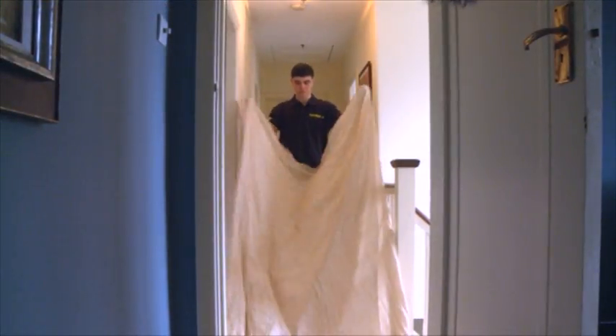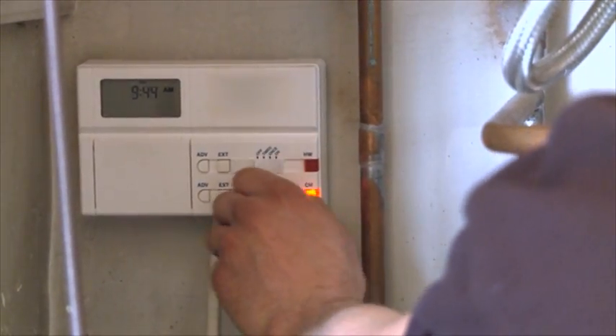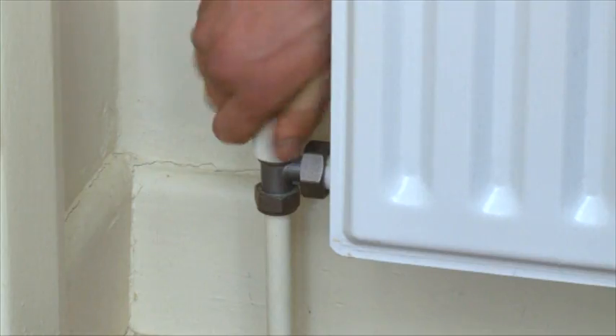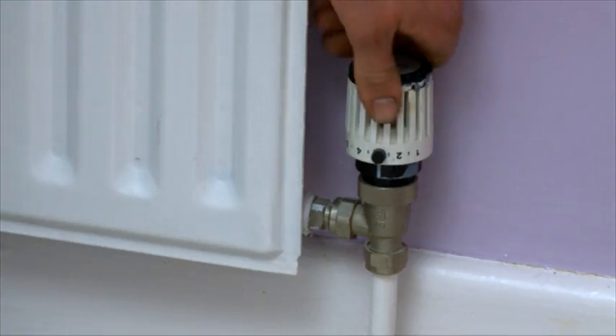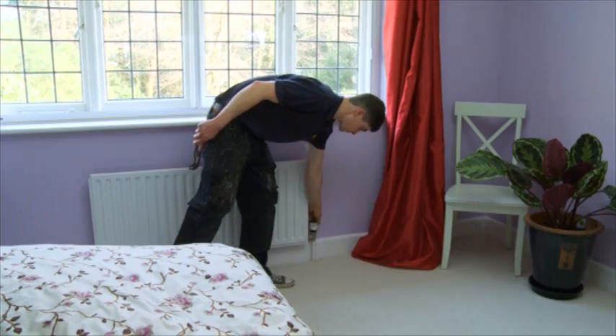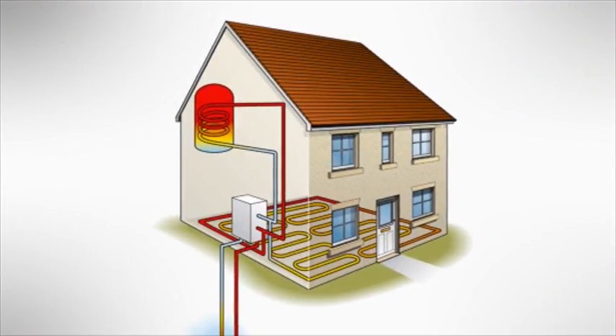Regarding the actual flushing process, firstly ensure that the system is correctly set up to use the power flush unit. Turn off all electrical controls and electrically isolate the system. Ensure that all radiator wheel head and lock shield valves are fully open, and remember to make a note of their position. Check that all thermostatic radiator valves or TRV heads are either set to maximum or removed, and that all zone valves and three port valves are locked open. Any anti-gravity valves should be bridged, bypassed or temporarily removed. Thermal store cylinders must also be isolated.